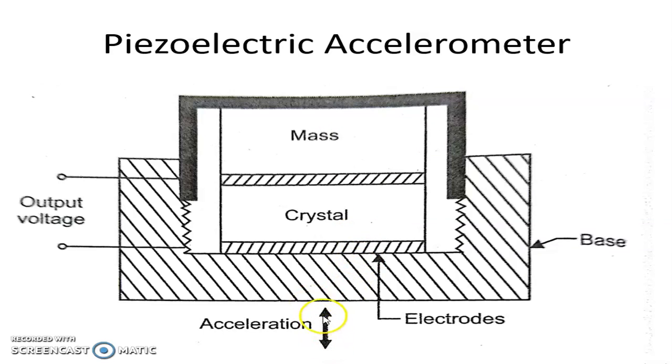As the acceleration applied to the base increases, the force applied to the piezoelectric crystal also increases, and more voltage will be developed across its surfaces. Therefore, the voltage developed is directly proportional to the acceleration, so the applied acceleration can be measured in terms of the output voltage.